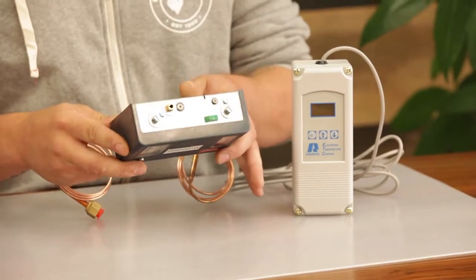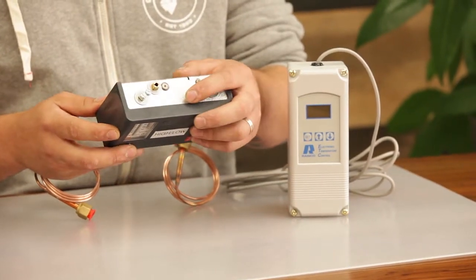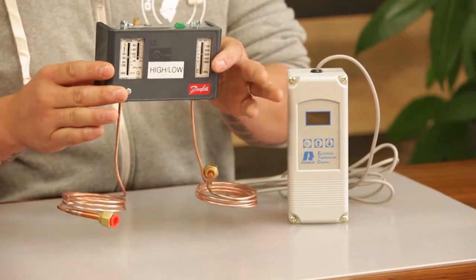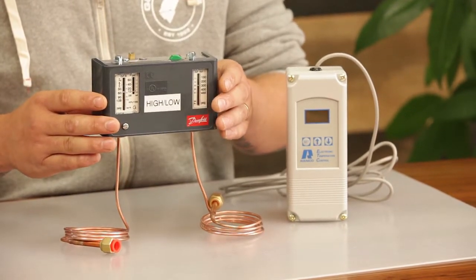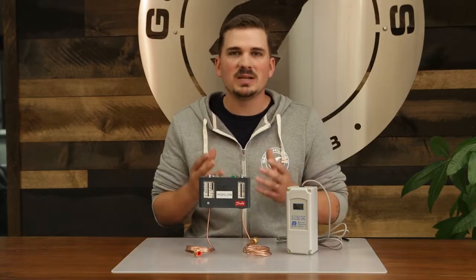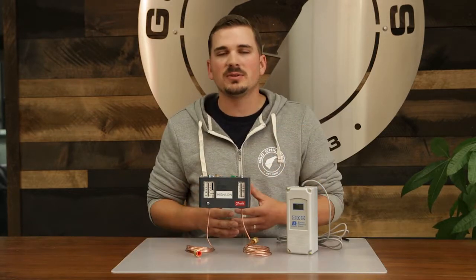There is a reset right on top of this thing. It's spring loaded. If you slide that over and let it go, that'll reset that high pressure switch in the event that it trips. Also, what can happen is, say it's midnight, there's nobody around, it's a Saturday, everyone's gone.